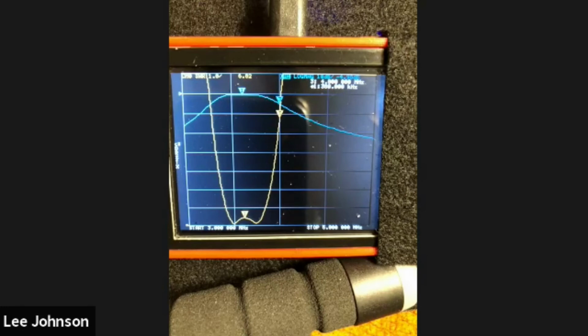Because one of the things you've got to remember, and I keep forgetting to mention it, is whenever you turn the unit off, the only thing that's going to come back is that C0 memory location for the calibration parameters. So if you've calibrated for 0 to 30, let's say, and you've in the meantime calibrated something else, but you didn't save it into the C0 location, it's going to evaporate when you turn the unit off. Okay, so don't forget that. So you only have one storage location that is going to be remembered by the firmware and come back up as calibrated in that particular point.